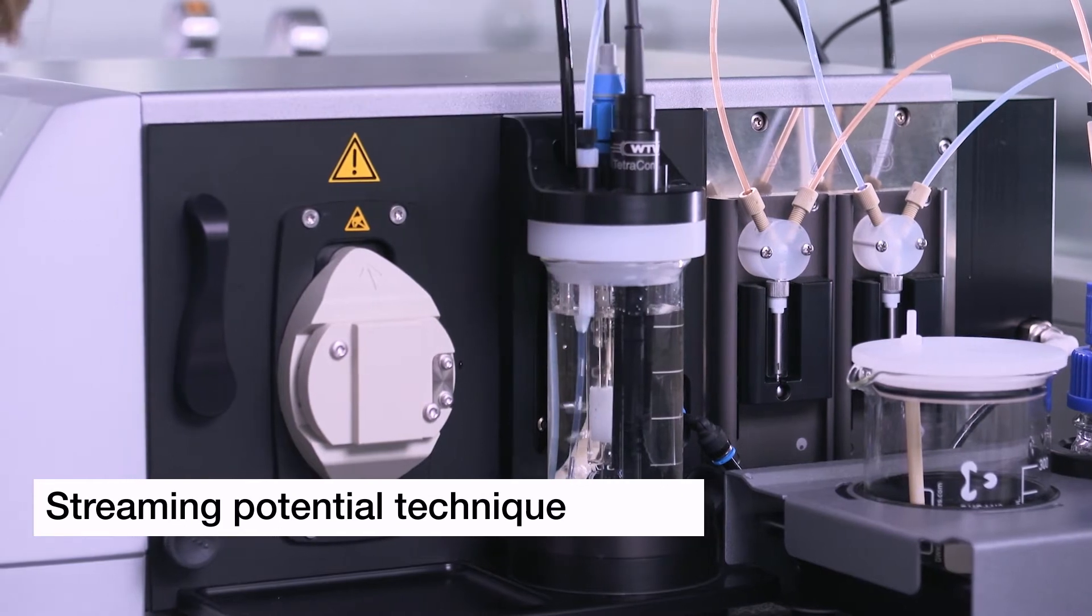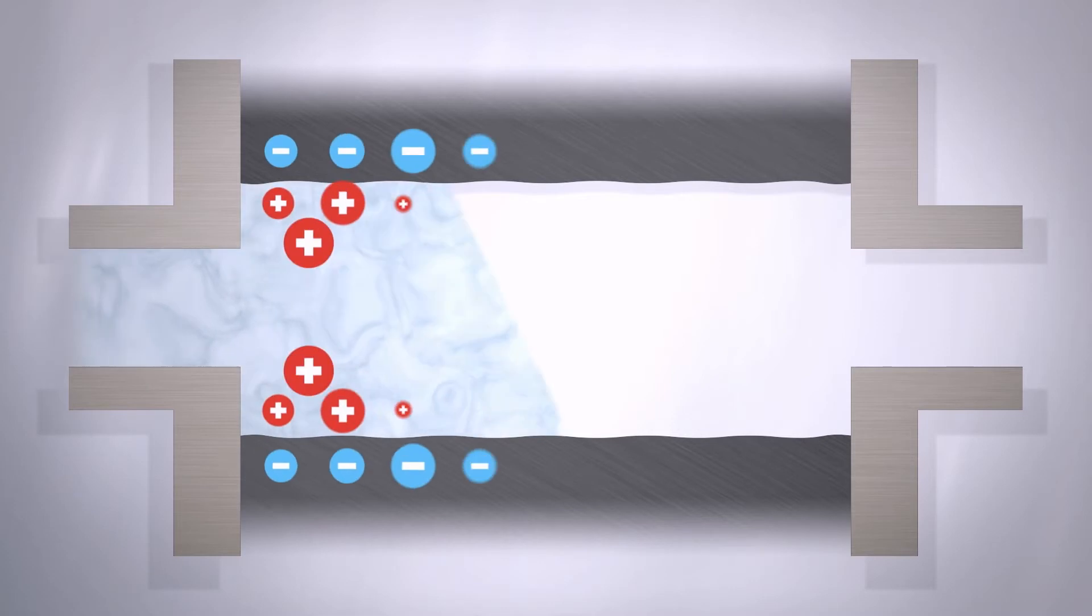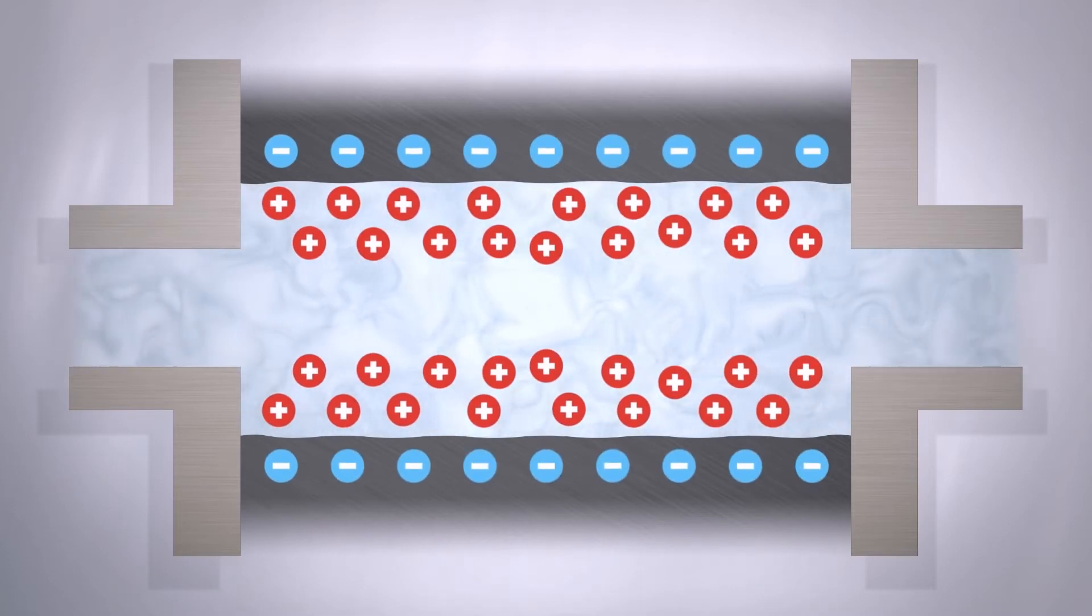The streaming potential technique is used for the zeta potential analysis of macroscopic solids. To do this, the sample is mounted on a suitable measuring cell so that a capillary channel is created. Once the solid surface is in contact with an aqueous electrolyte solution, charges are formed due to acid or base interactions.